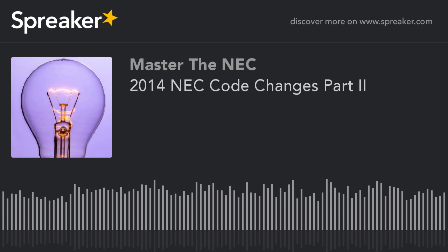The next change we're looking at sparked a lot of debate, and I'm sure it may change a little bit for the 2017 NEC. In fact, I am on Code Making Panel 17, and I am more than sure that there is an attempt to move this requirement that I'm getting ready to talk about up under 422 for appliances. But here we're looking at 210.8(D), and that is for dwelling unit kitchen dishwasher branch circuits. Okay, so it only applies to dwelling unit applications.